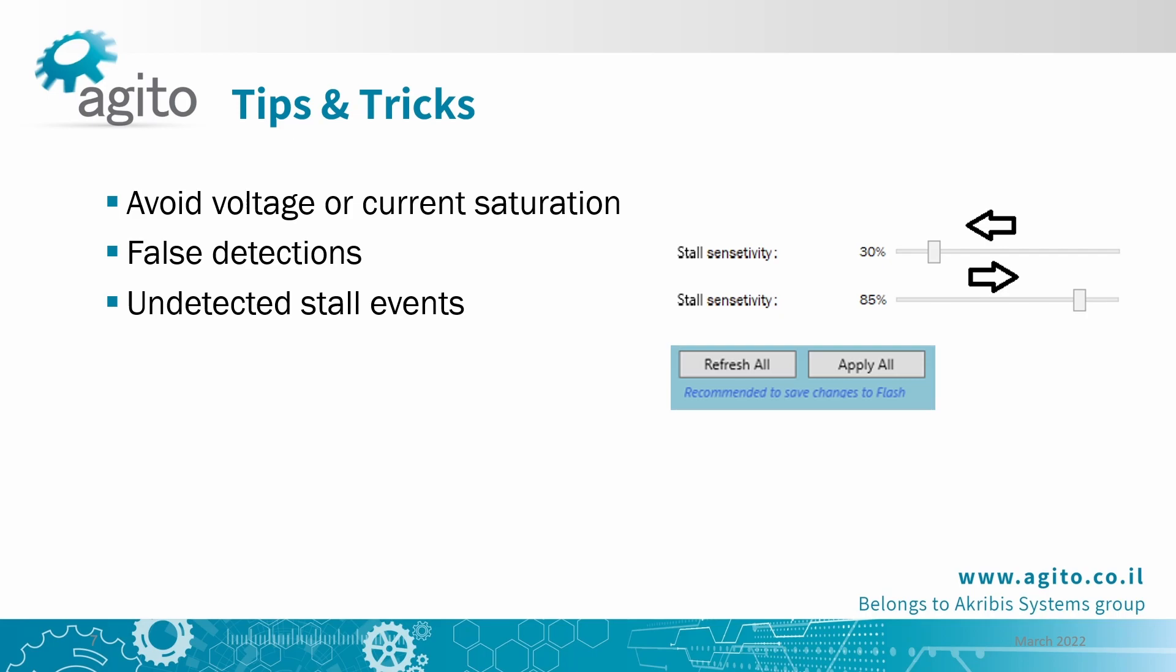Make sure to click the apply all button after any change in the sensitivity. Consider recalibrating in both cases. To test the feature after recalibrating, set the motor to jog mode and stop it mechanically if you can. Or set the speed to an extremely high value to cause a stall event, just like we showed in the examples earlier.